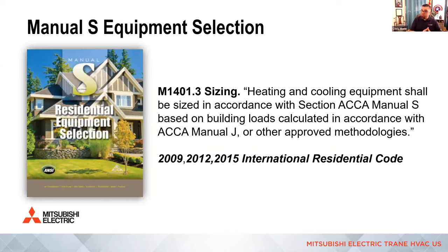Obviously, in order to select the right equipment, you should be following ACCA Manual S, and this is what is code in the International Residential Code. I'm not going to read what's on the screen. Basically, you size the system based on Manual J, and you select the correct size based on Manual S without drastic oversizing, right? So this applies to every heating and cooling piece of equipment. There's minimums and maximums as you go.